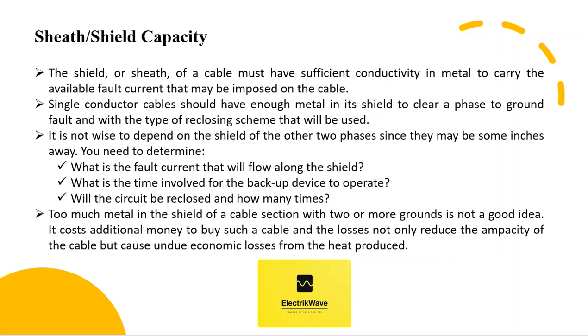The shield or sheath of a cable must have sufficient conductivity in metal to carry the available fault current that may be imposed on the cable. Single conductor cables should have enough metal in its shield to clear a phase-to-ground fault, given the type of re-closing scheme that will be used. It is not wise to depend on the shield of the other two phases since they may be some inches away.